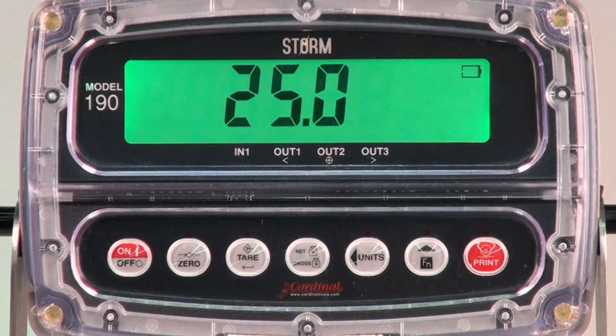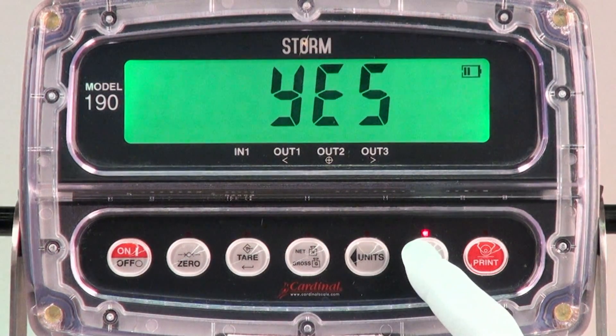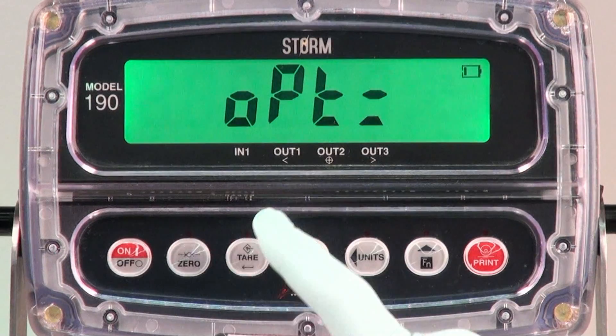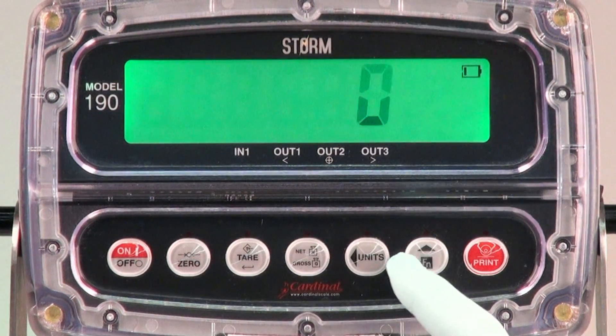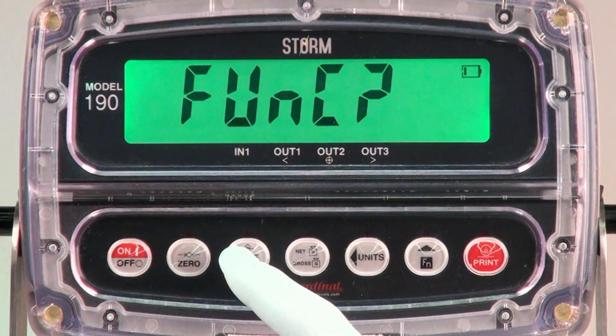The tare key is utilized as the enter key. Moving into the function settings, you can easily turn on or off the function for the application required. Here we are turning off the option card feature OPT by changing the entry to zero using the arrow up key, and then touching tare to save the setting.